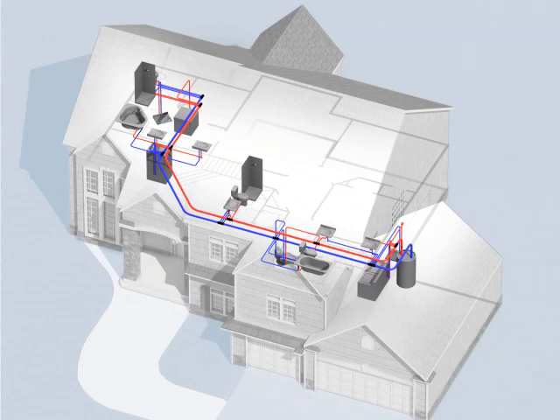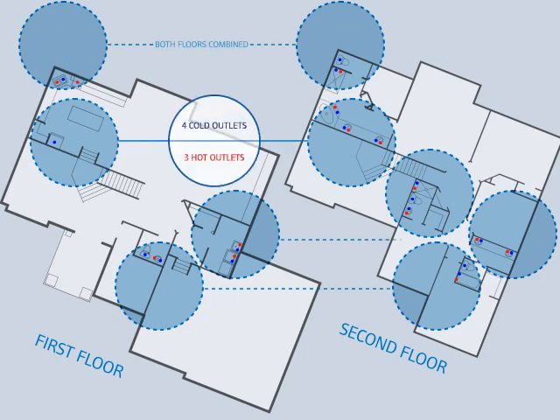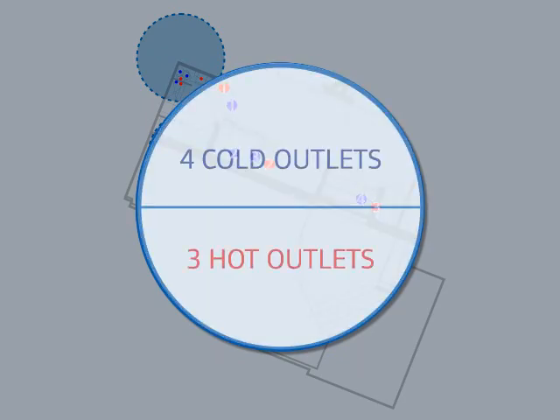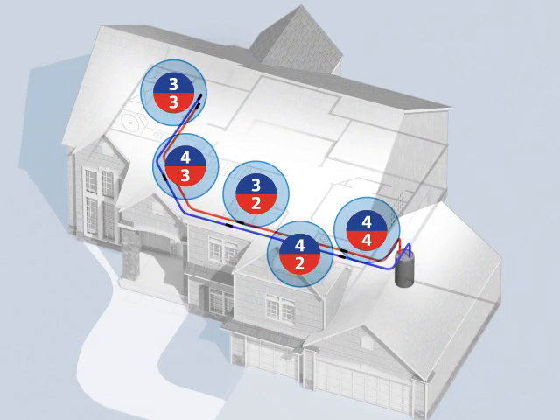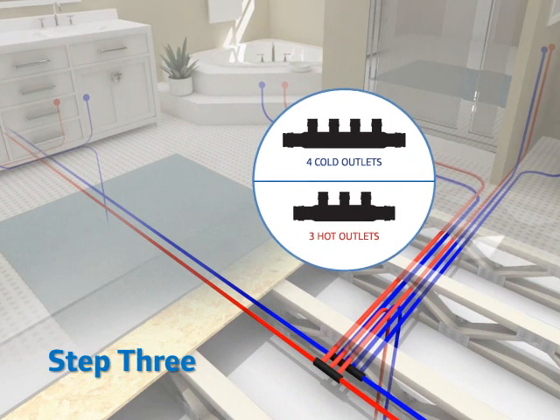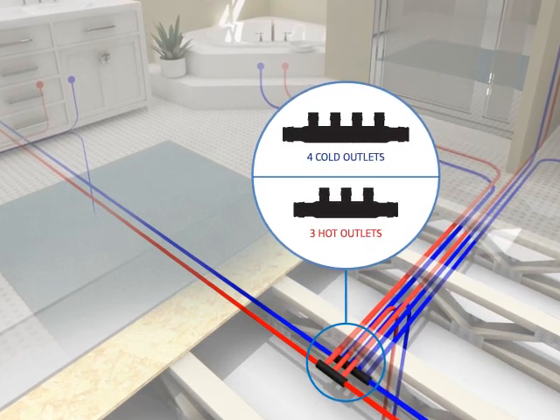To begin using the Uponor Logic system, simply follow our three-step planning process. Using your building plans, identify the location of all plumbing outlets and hot and cold water fixtures. Mark all fixture groupings that fall within an approximate 10-foot radius of one another on each floor, as they can use a common hot or cold supply line. Chart the most direct supply line path through the floor plan to connect all your fixture groupings. Finally, select the proper location for the multi-port tee for each fixture grouping. Maximizing your multi-port tees reduces fitting needs as well as the fixture connections.